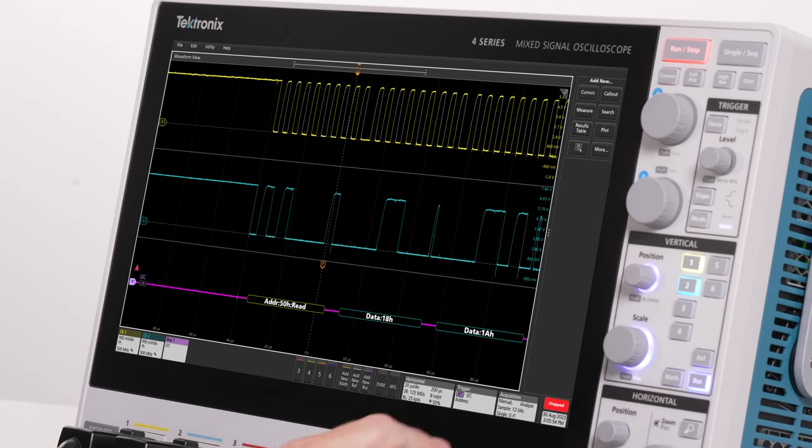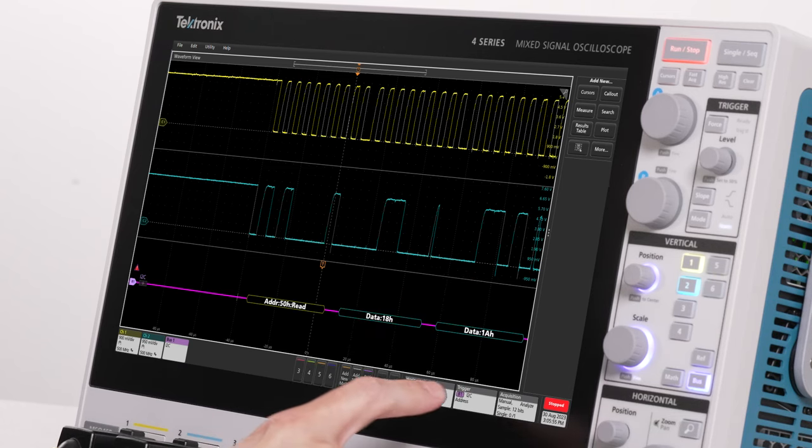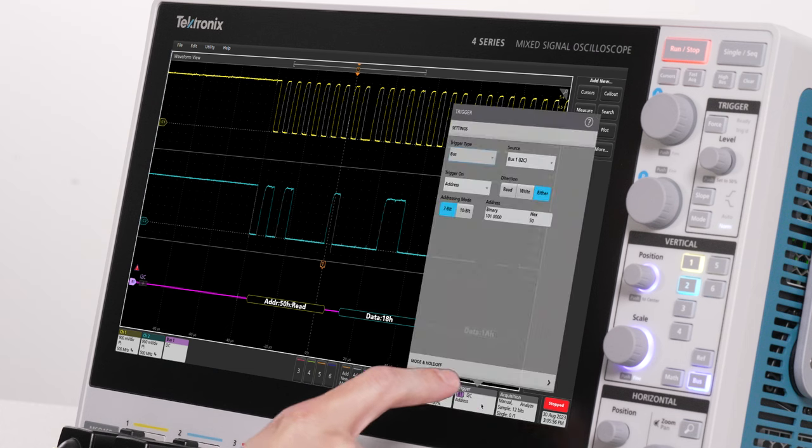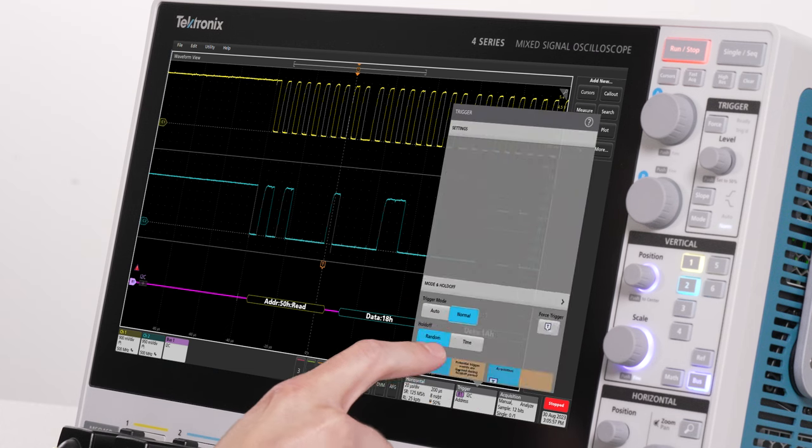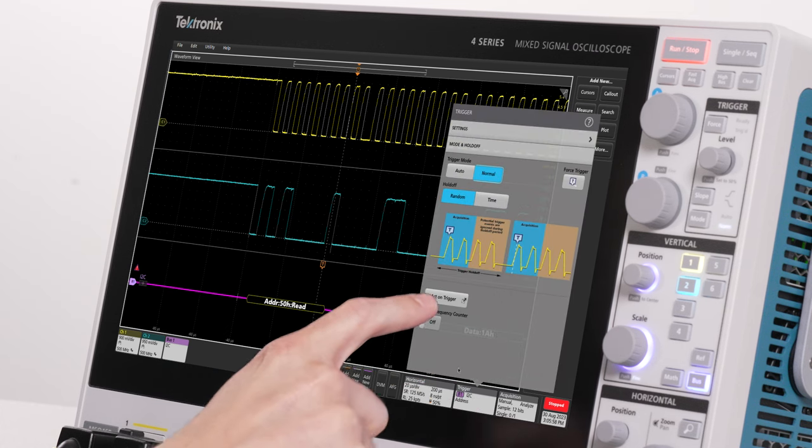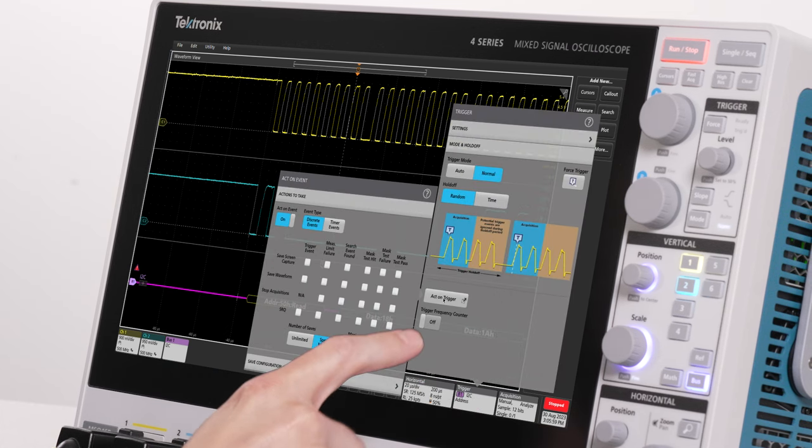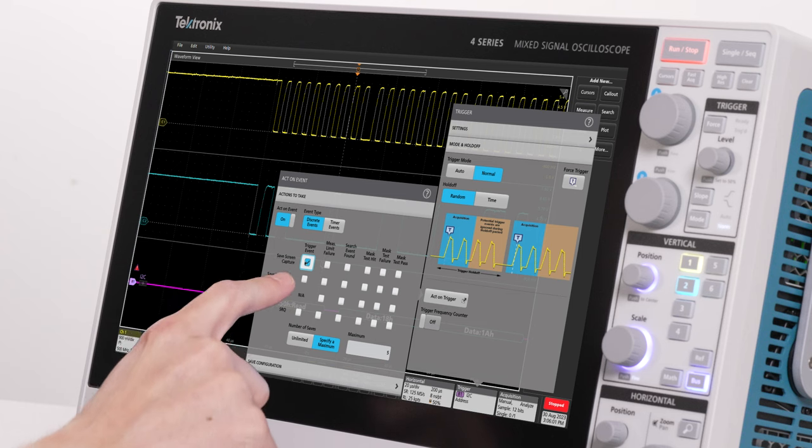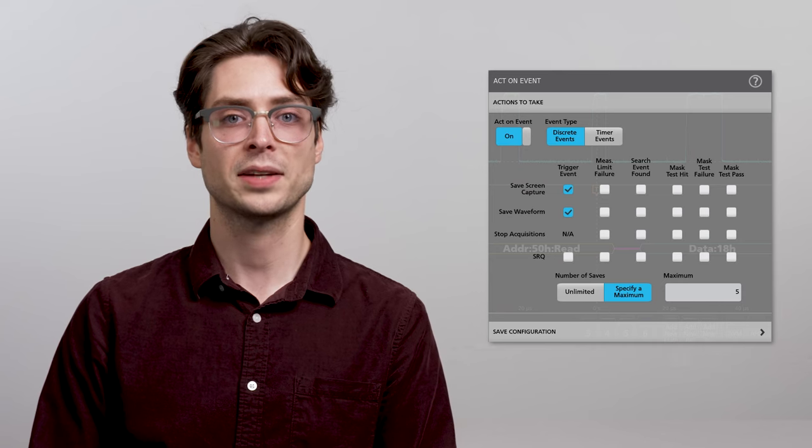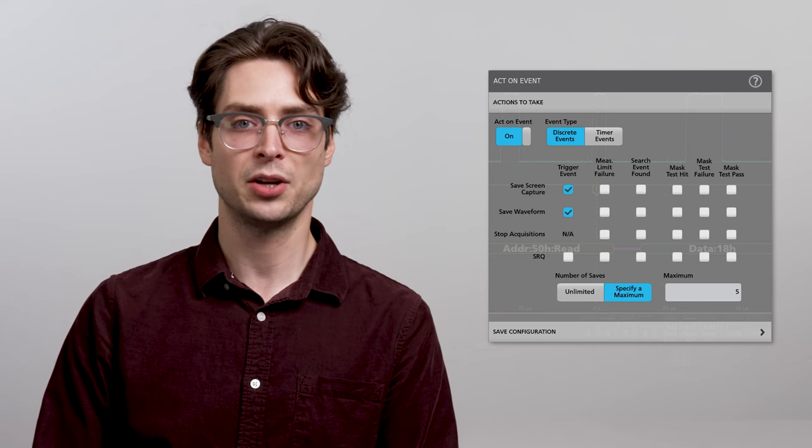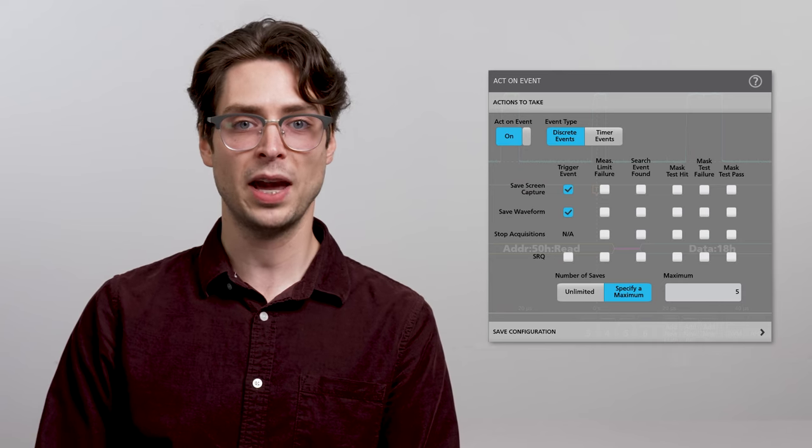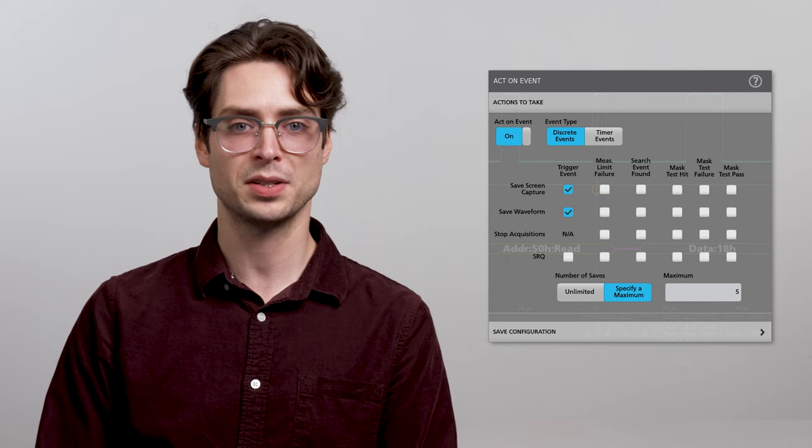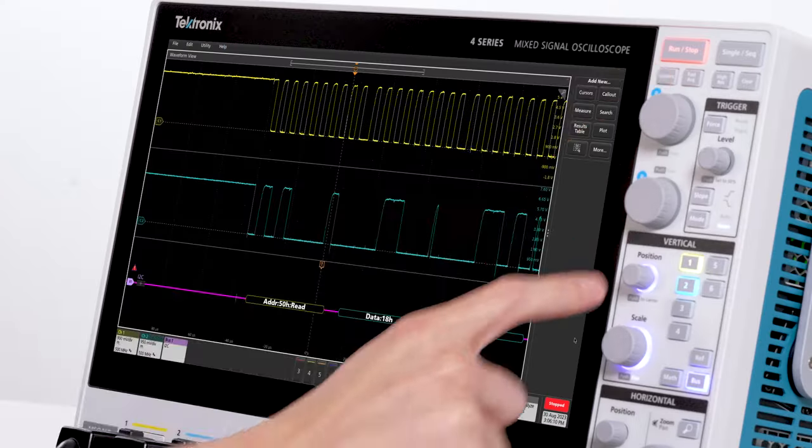Say I want to store some packets that access that address. The 4 Series B can save screenshots and waveforms based on events like triggers, search results, or limit and mask test results. Act on event allows you to automate specific actions in response to signal events.